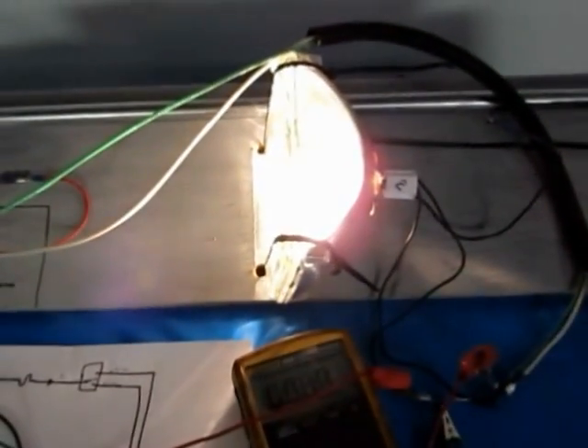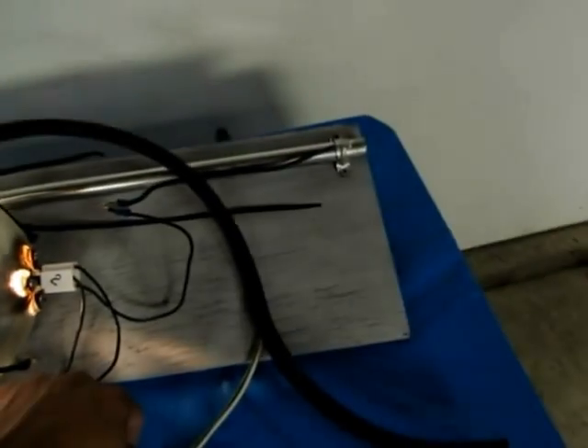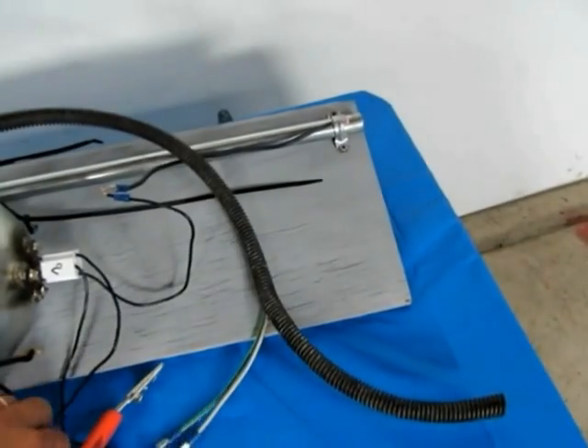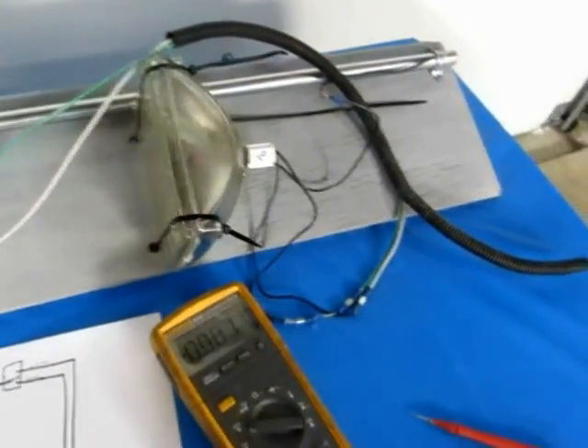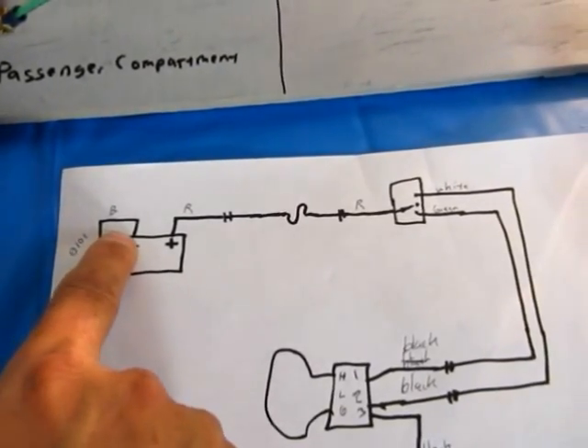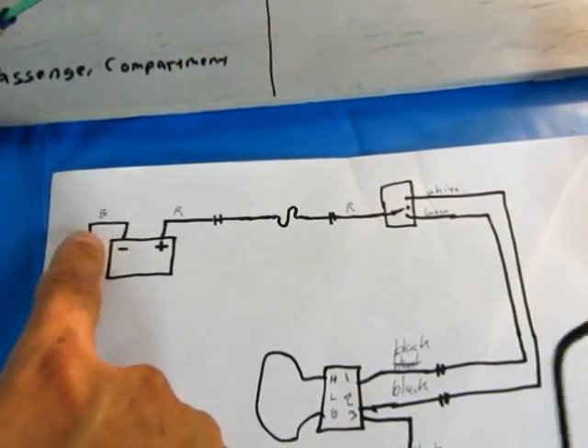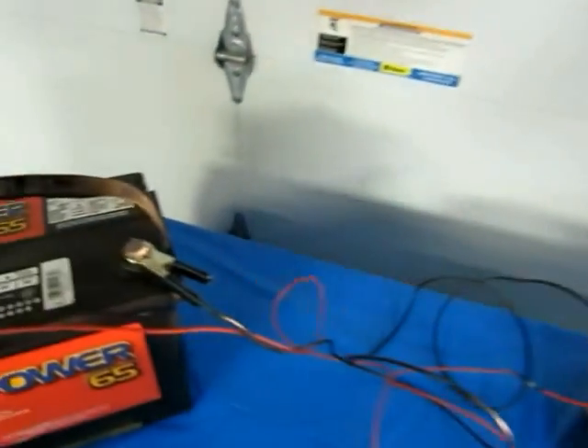That's just one way of showing you how to do a voltage drop test. A voltage drop can be on the ground side of a circuit, it can be on the power side of a circuit, but you always have to remember, always test the circuit live. That means have it powered up and running. If you wanted to do a voltage drop test on the ground side of the circuit, you'd have to put your meter to the battery negative and then trace back on your ground, which the ground on this, like I said, is a piece of EMT tubing. It's kind of rough, I know, but it gets the point across.